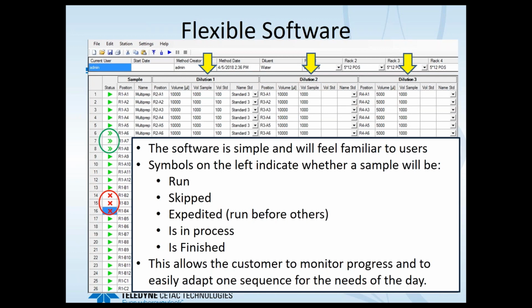The software itself is very spreadsheet-like. I mean, you can see here across the top, we've got dilutions 1, 2, and 3. And then on the side, you can see all the arrows. I've highlighted a couple specific spots. And they allow you to expedite a sample, so that if something comes in that you decide you need to run right away, you can select that specific sample to be run out of sequence, and it'll do the expedited samples first and then resume where it was in the run. And you can also exclude samples, which is really nice if you have variation from day to day. One day you have 30 samples, the next day you only have 15. You can use the exact same sequence and just take out whatever samples you don't have to run on that given day, and you don't have to go through rebuilding the process or changing the files.